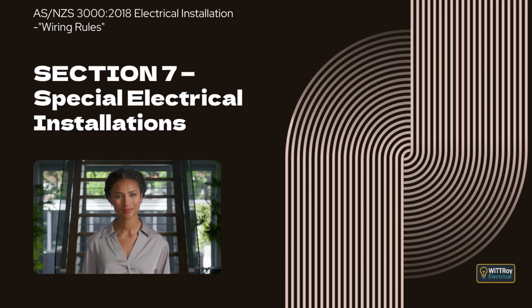It states that in these cases, the wiring system must either be able to keep supplying power when exposed to fire or mechanical damage, or be protected so that fire or mechanical damage will not prevent it from supplying the equipment. It explains that this can be achieved by suitable enclosures or by locating the wiring where it will not be exposed to damage. The clause also explains that conductors supplying safety services must be physically separated from other wiring systems by a minimum distance or by suitable barriers, and must also be separated from other safety services. It further explains that conductors for different safety services must not be combined together within the same multi-core cable, and must not be combined with conductors of other wiring systems.